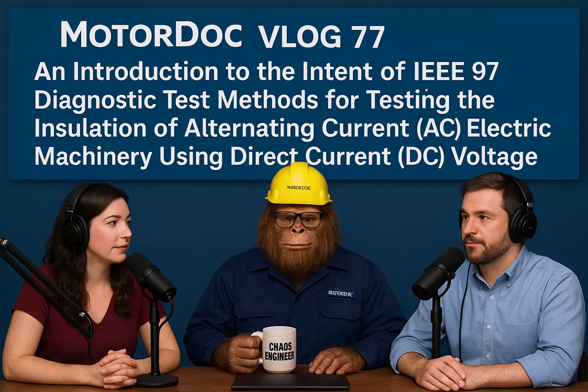Does the voltage level itself influence PDC interpretation? It can. For healthy insulation, the PDC values, like resistance, should generally scale linearly with the applied voltage. But the guide shows that with degradation, the PDC response can become nonlinear with voltage. Meaning the measured insulation resistance effectively decreases as you increase the test voltage. They show examples comparing the nice linear response of a healthy bar to the nonlinear response of an aged winding, where the resistance drops off at higher test voltages.